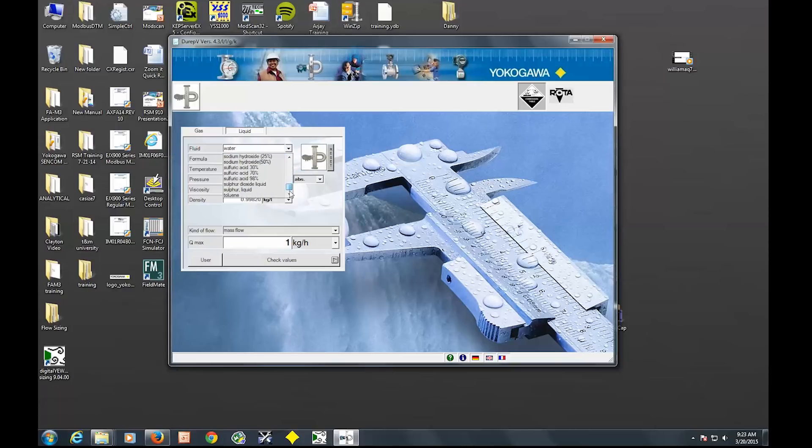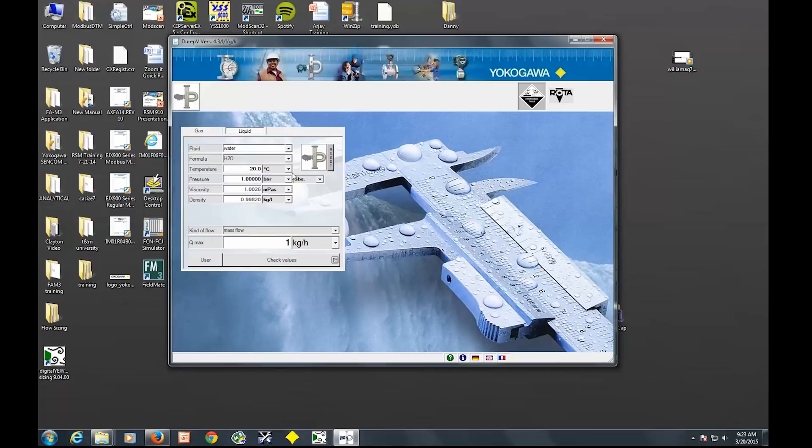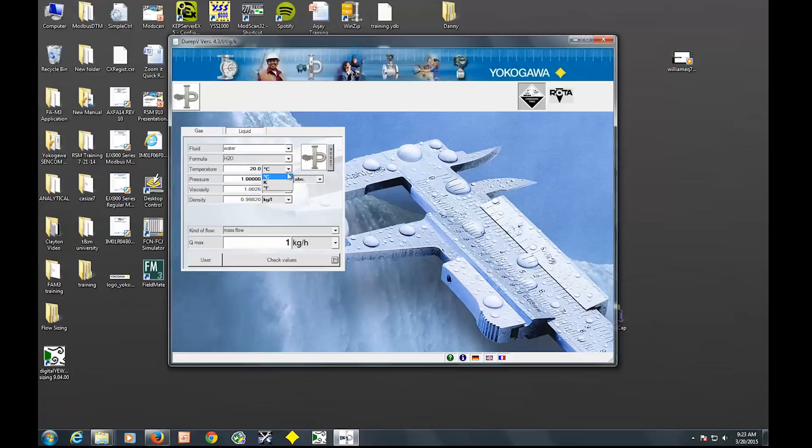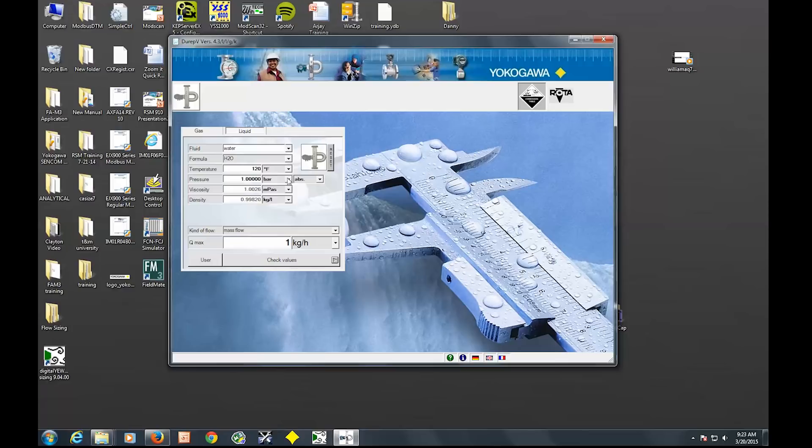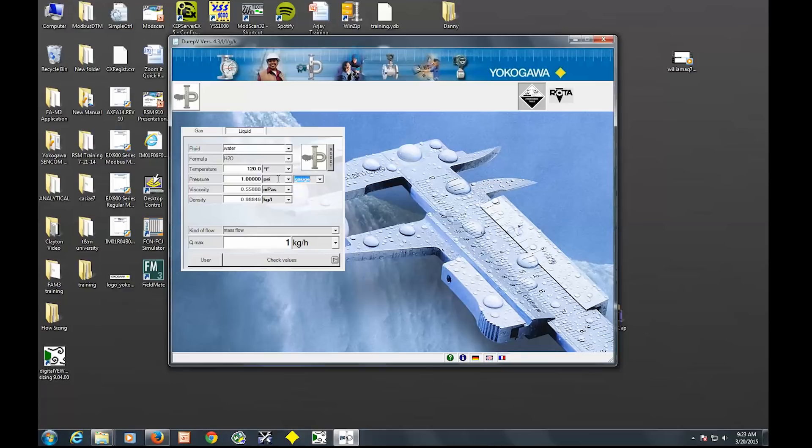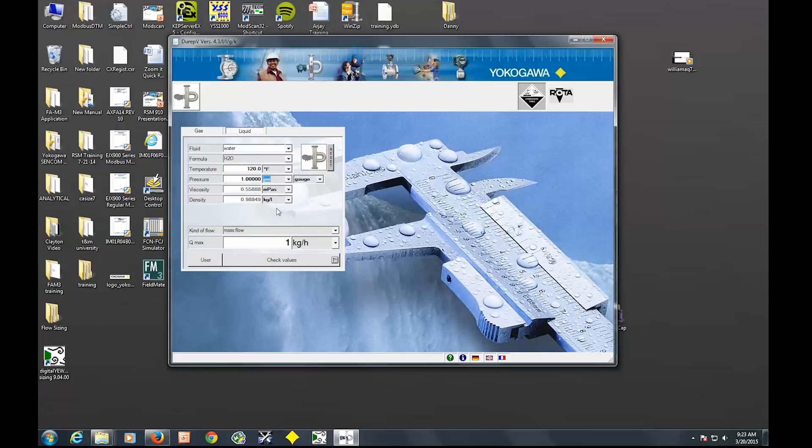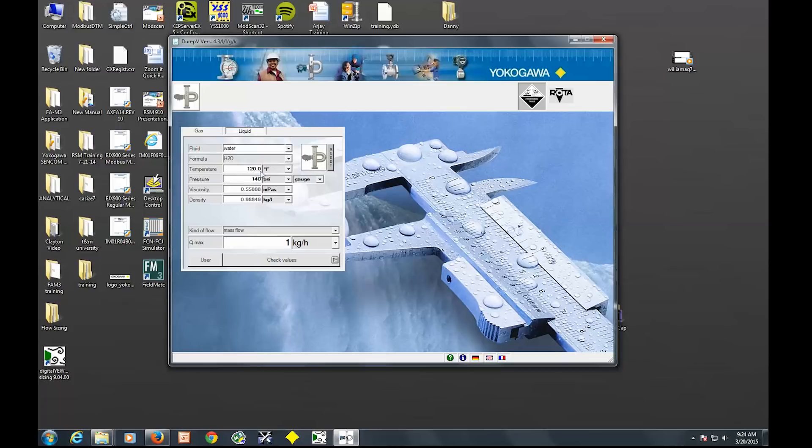So this drop down has a list of a lot of fluids that we have properties saved for. Once you put in your temperature and pressure it's going to give you a viscosity and density. So I'm just going to put my max for everything. I'm going to change this unit to Fahrenheit and then my max is 120. And then my max pressure, I'm going to change my unit to PSI gauge. You see my viscosity and density changed once I put in my temperature and pressure.